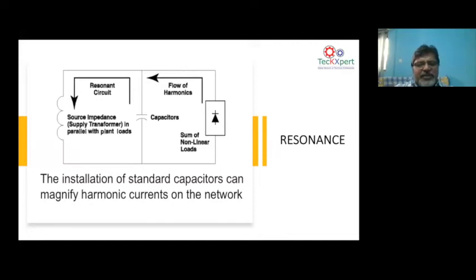In an equivalent diagram, in the electrical engineering way, we explain this. If you look at this equivalent circuit, it shows a harmonic producing load. That is a current source. Ultimately, as I told you before, harmonics come under current distortion. You connect a voltage, and if the device is nonlinear, it starts drawing a nonlinear current. So harmonics are always considered in terms of a current. It's a harmonic current source.